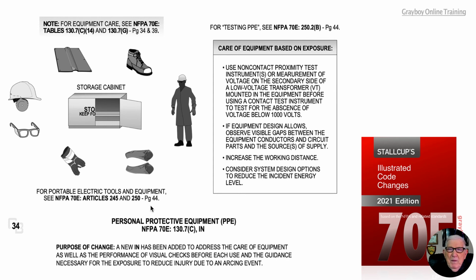Now, the basic informational note states, as we see in the illustration here with the title head, care of equipment based on exposure. Use non-contact proximity test instruments or measurement of voltage on the secondary side of a low voltage transformer mounted in the equipment before using a contact test instrument to test for the absence of voltage below 1000 volts. We know 1000 volts or less is considered basically low voltage. Over 1000 volts is then considered high voltage and medium voltage and so forth.